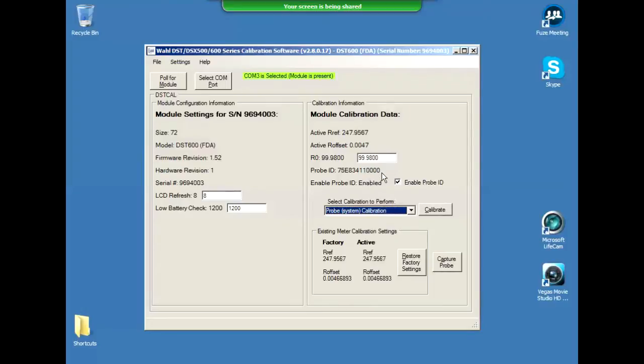We can disable that, and that's a checkbox again. And what that does is that is for if you're running cables and we've had customers that have ordered 100 meters of cable, a couple 100 meters of cable. If you're anything over 30 meters, you will need to disable that, because the driver, that chip that's used in here, just can't drive that signal on that much wire. That length of wire, the resistance gets to it. So that's what the enable probe ID is.